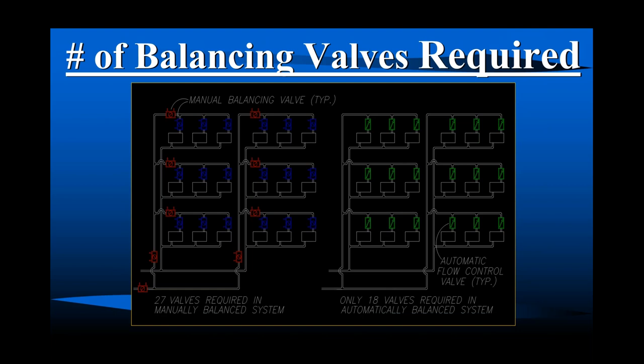And what happens if we use manual balancing valves on all these terminal units, or we use automatic flow balancing valves? So here are our terminal units. And in this system, how manual balancing valves work is if this is a 3 GPM terminal unit, design day flow is 3, right? We have to touch this red one right here. We have to make 9 go down this runout. And then we have to touch this one to make 3 go there and 3 go there and 3 go there. Same thing for here. You have to make a certain GPM go through here and there on this branch. So we have to finish the risers, then the runouts, and each individual terminal unit. So to do this right on this type of system, we need 27 valves.